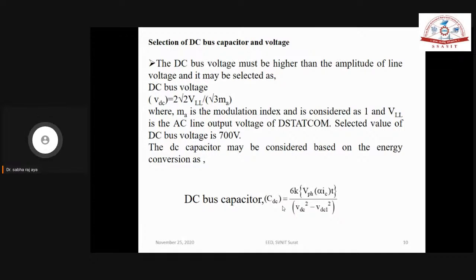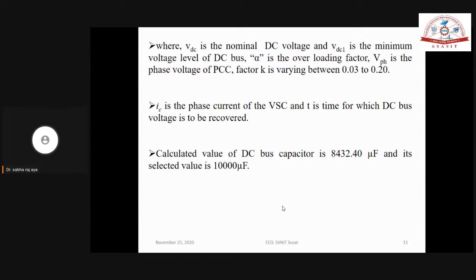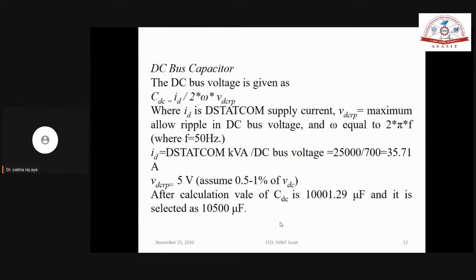T is the time required during a disturbance to recover the DC link. Generally we take 300 to 500 microseconds as this recovery time. Now based on this data we can calculate the DC link. Here we got 8432, some value. This is random data we have put. You can also put values according to your requirement and your design.